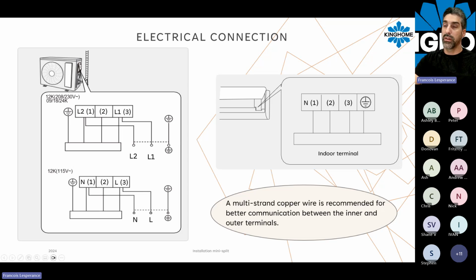The outdoor board located here will send out the communication to the indoor board here on the indoor unit. So terminal number 2 here is your communication line. The signal will be sent out by terminal number 2, received here on the indoor portion, and also transmitted back to the outdoor unit by terminal number 1. So terminal number 1 will receive the information, so it will be a back and forth between number 1 and number 2. Both terminals are used for your communication. So whenever you have an issue with the communication wire, you have to look at those two terminals, make sure the connection is good, and also make sure you have the proper voltage.